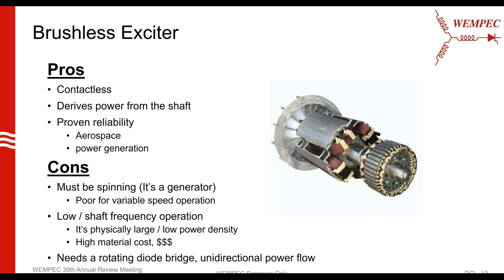Yeah. So the brushless exciter, this is what's used in standby generator sets. It's contactless. It delivers power from the shaft, so it turns the torque and speed from the prime mover, say an engine in a genset, into the field power. It's another generator on the shaft powering the field of a larger generator. It's large for what it is, but that's acceptable in applications where you have a prime mover like an engine and a genset, but it's physically large and not suitable for a traction drive. Note that it does have a rotating diode bridge.